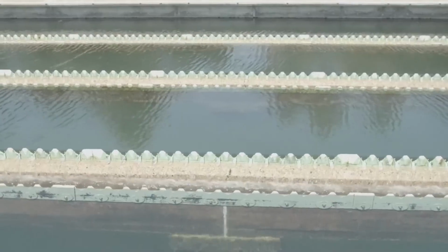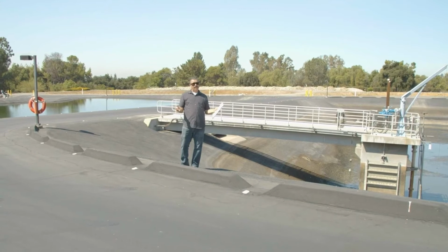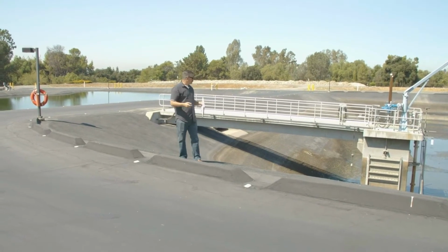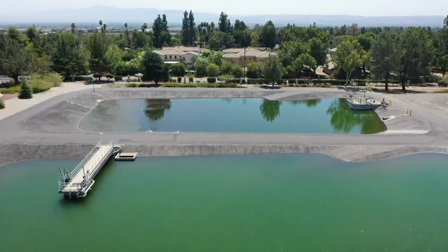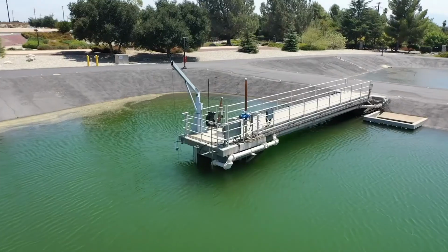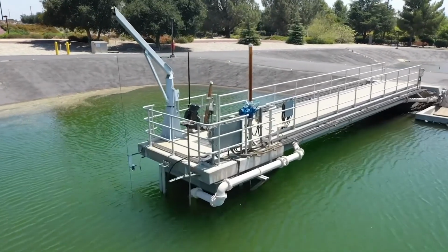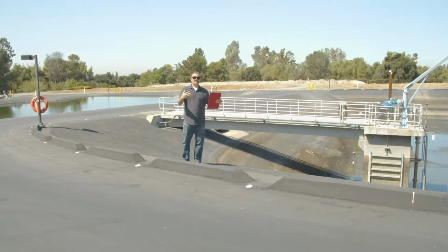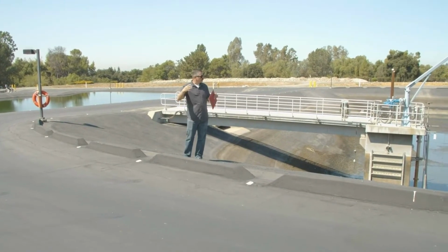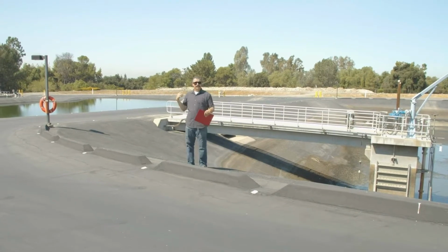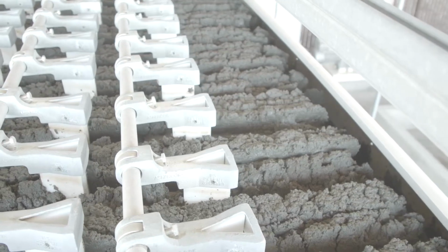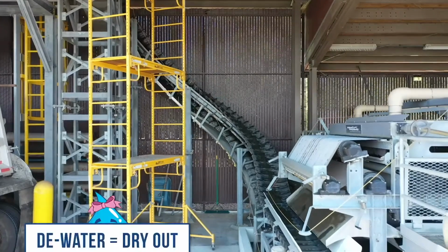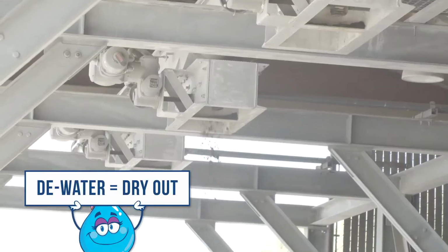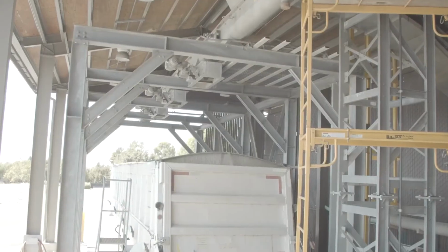We talked a little bit about the flocculation process, sedimentation, and the filtration process. We also discussed the disinfection process, and now, as you can imagine, behind me what you see are what we call the sludge ponds. At each one of those stages, there are different materials or sludge that have to be removed and relocated, and that gets relocated to these points here. We push the sludge over to the belt filter press so that we can dewater the sludge, recycle that water, and then take the solids and haul it off site.